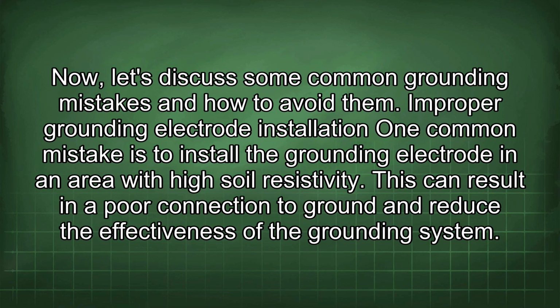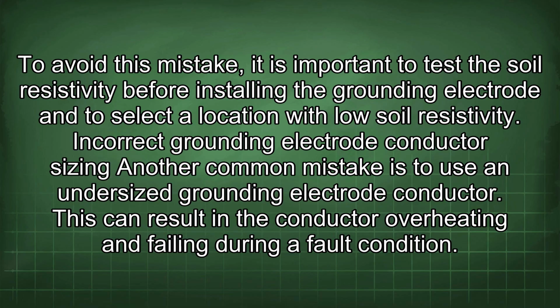Now, let's discuss some common grounding mistakes and how to avoid them. Improper grounding electrode installation. One common mistake is to install the grounding electrode in an area with high soil resistivity. This can result in a poor connection to ground and reduce the effectiveness of the grounding system. To avoid this mistake, it is important to test the soil resistivity before installing the grounding electrode and to select a location with low soil resistivity.